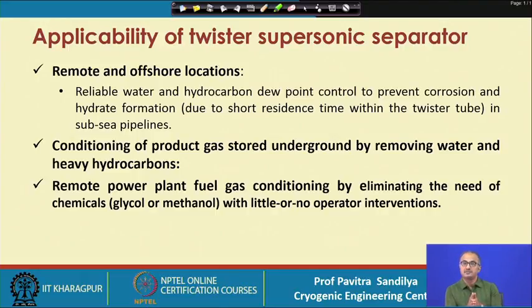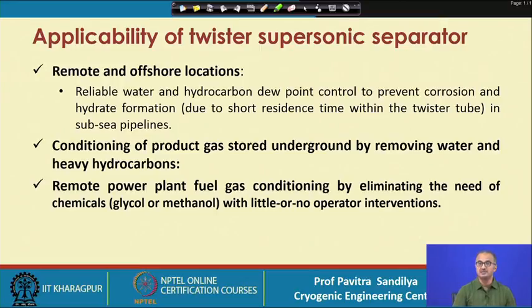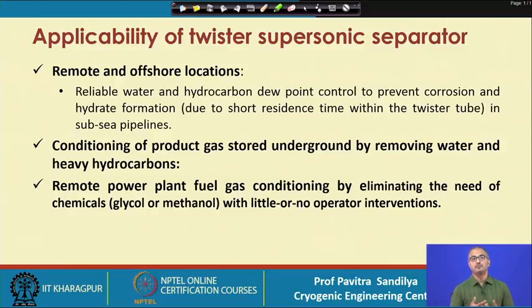The twister supersonic separator is particularly suited for remote and offshore locations for reliable water and hydrocarbon dew point control to prevent corrosion and hydrate formation — with very little contact time between hydrocarbons and water, the possibility of hydrate formation is reduced. It is used for conditioning product gas from underground by removing water and heavy hydrocarbons, and for remote power plant fuel gas conditioning, eliminating the need for external chemicals and operator interventions — a significant advantage in remote locations where chemical replenishment is not always feasible.